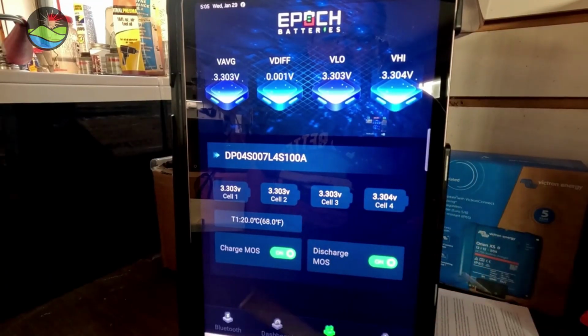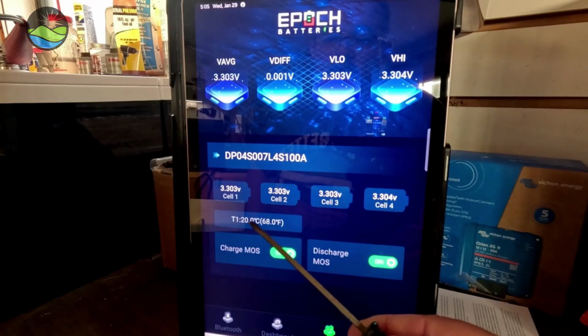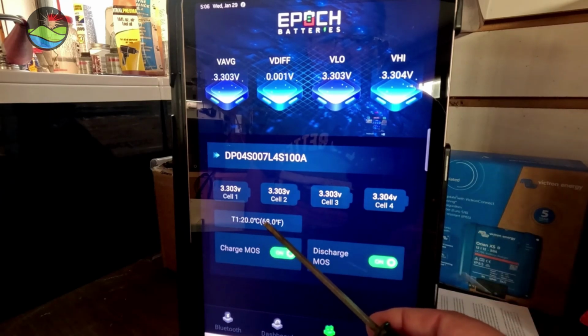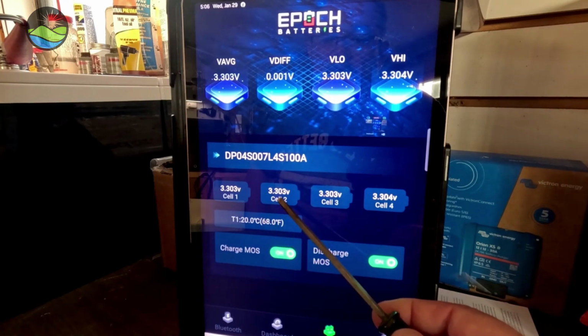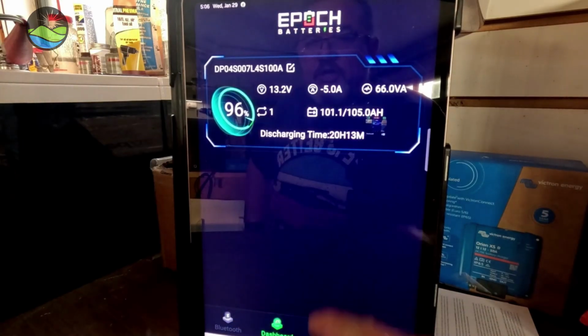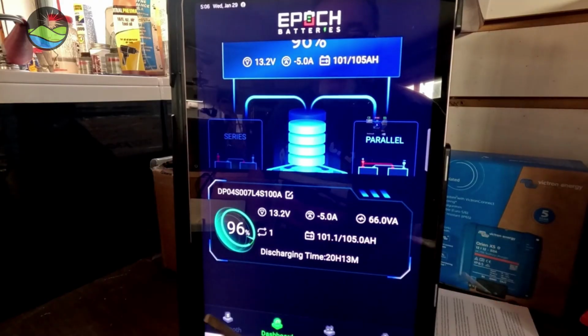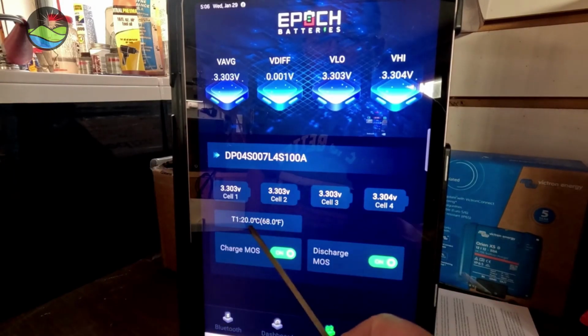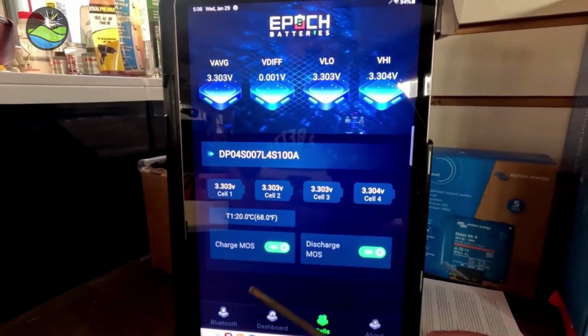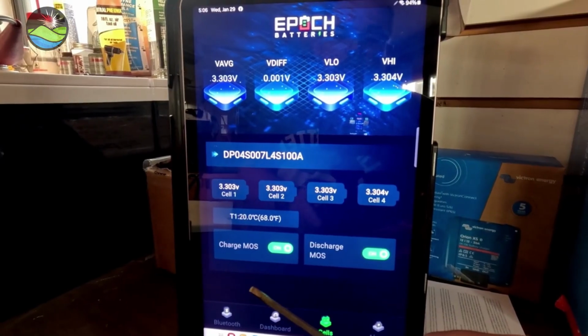There'll be a little fire icon somewhere indicating it's internally heating. Another thing about cold weather charging: once it's below 32 and you apply a charge, it has to raise the temperature above 41 before the cells will begin taking a charge, and you'd see amps coming in a positive fashion. So there's a hysteresis—if it drops below 32, it has to rise above 41 before the battery begins to take a charge. The reason is there's a lot of mass in these battery cells, so they want to make sure there's plenty of margin and that the cells are heated all the way through, so they set the threshold a bit higher.